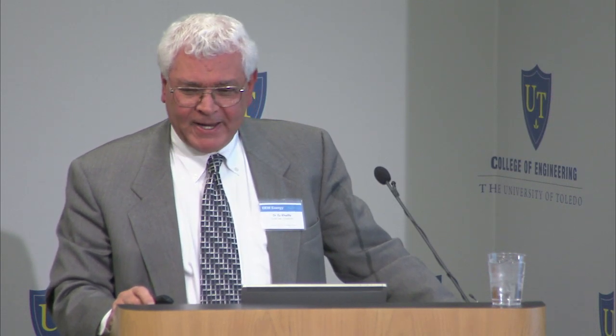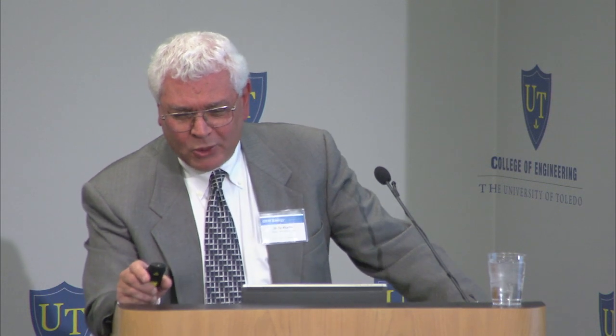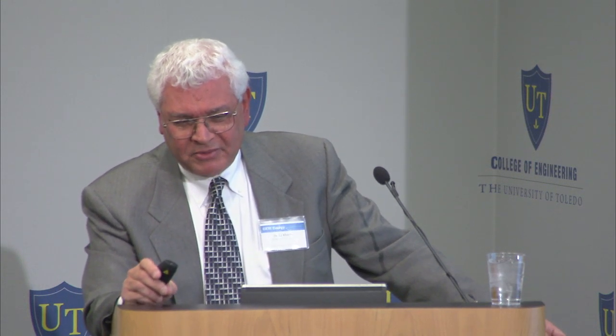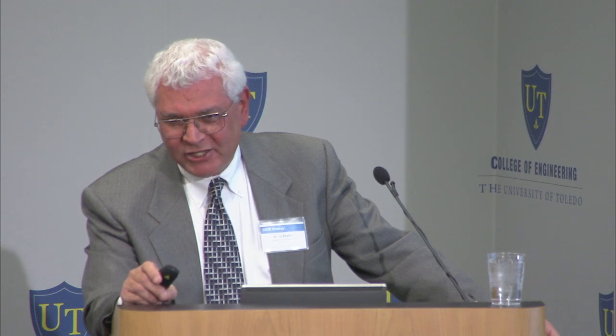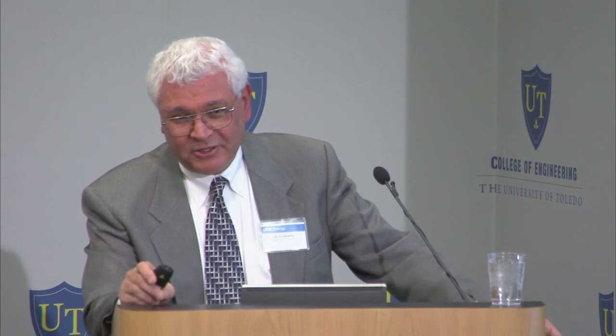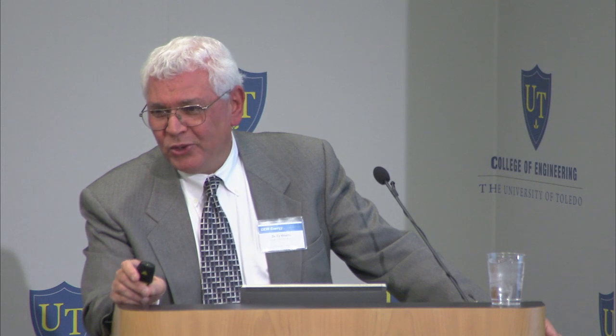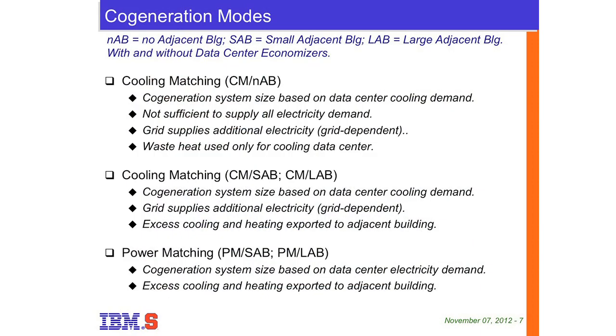We analyze it in a number of operating modes. In cogeneration, sometimes you size them to match the thermal load. So for a data center, the thermal load is a cooling load, so we call it cooling matching—you size the equipment so that its cooling output is matched to the data center. Or you can size it so that its power output is matched to the data center.